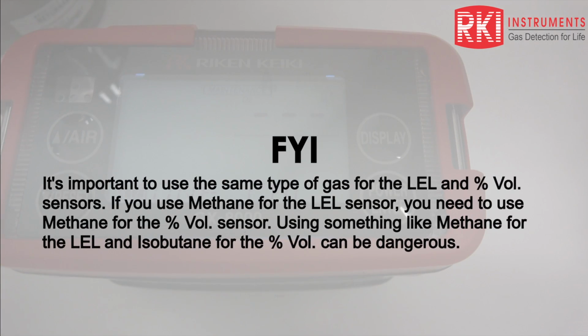It's important to use the same type of gas for the LEL and percent volume sensors. If you use methane for the LEL sensor, you need to use methane for the percent volume sensor. Using something like methane for the LEL and butane for the percent volume can be dangerous.